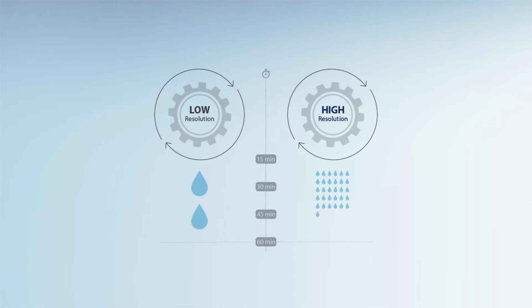Pumps with higher resolution of flow push a greater number of smaller boluses into the tubing to deliver the desired dose. Flow continuity, or continuity of flow, describes the continuousness of an infusion or the pump's ability to reduce those periods of no flow.